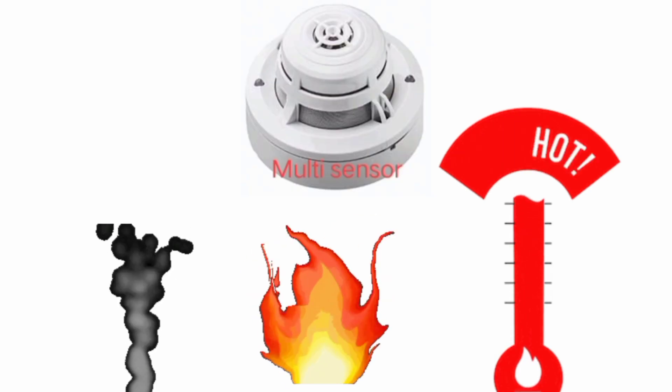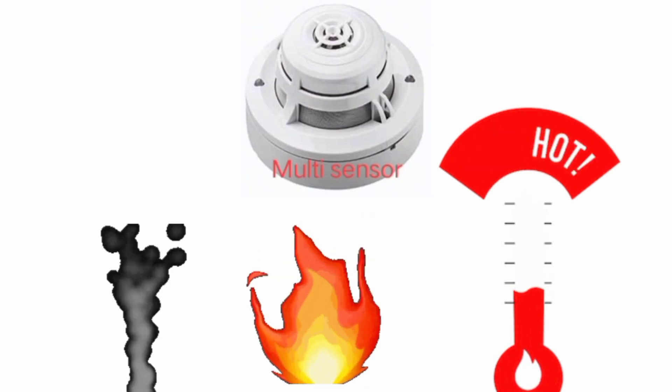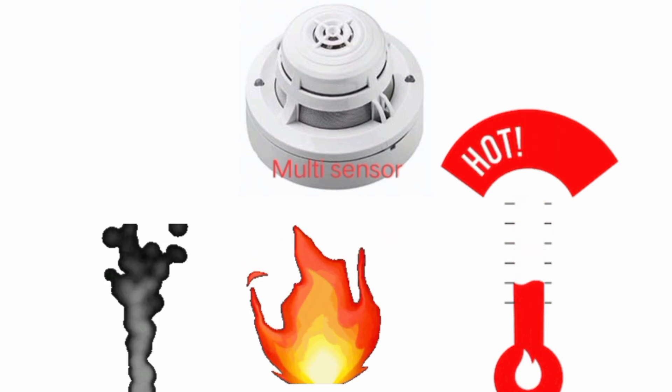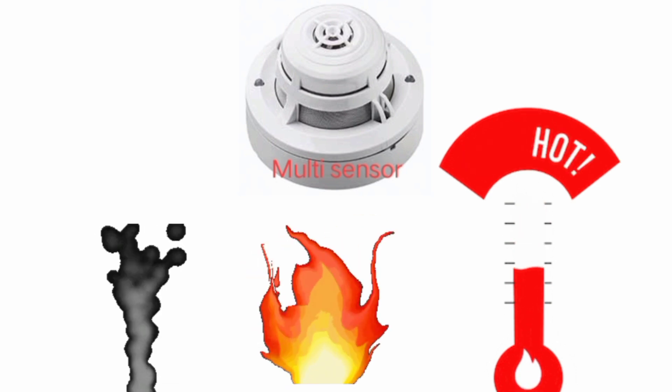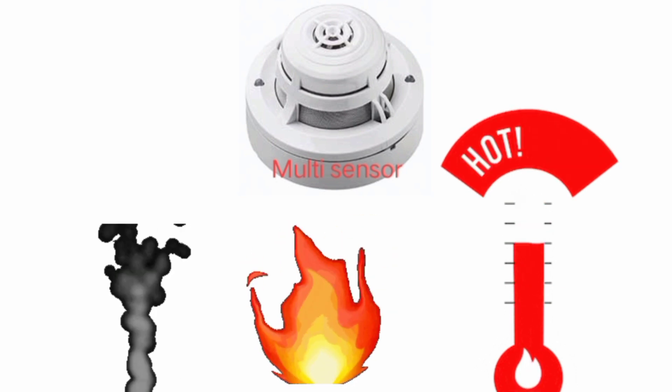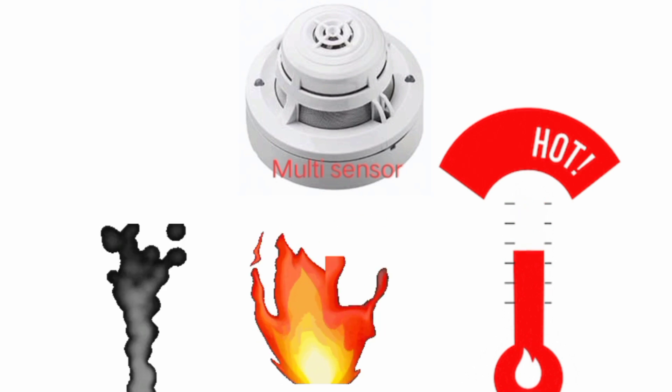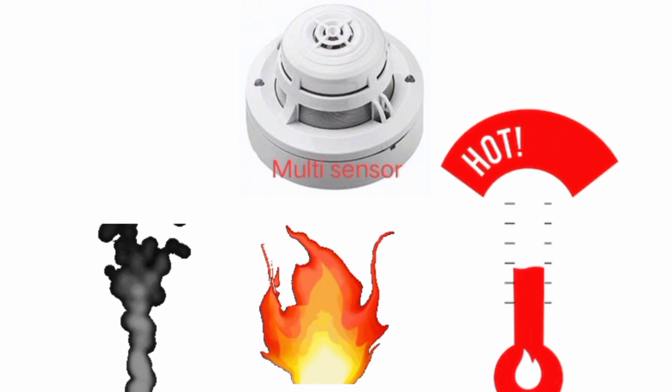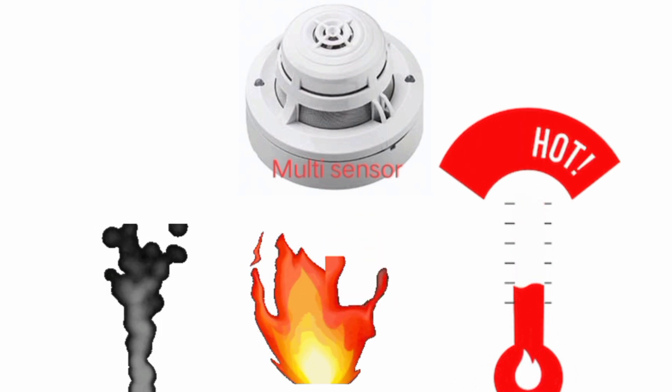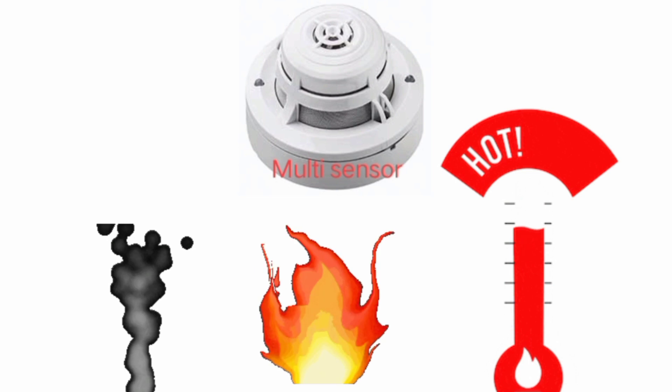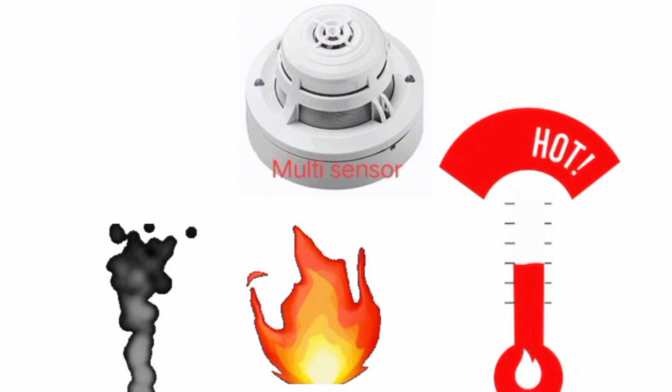Multi-sensor detectors are a combined optical smoke and heat detector allowing flexibility in the detection of fires. Using the combined detection method, a fire condition can be confirmed if both heat and smoke sensors operate. These detectors are general-purpose detectors which respond well to a wide range of fires.